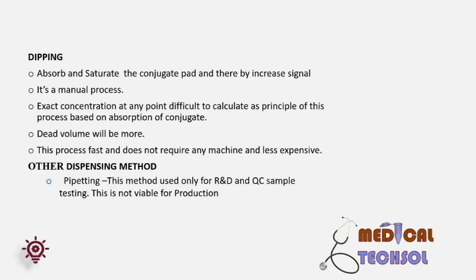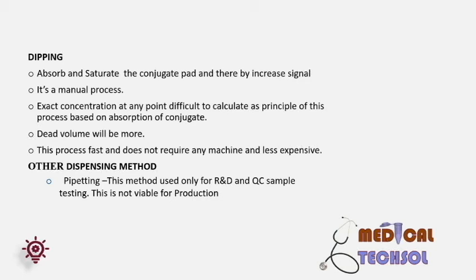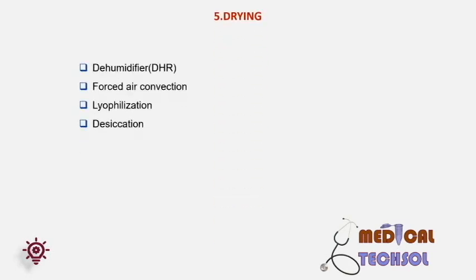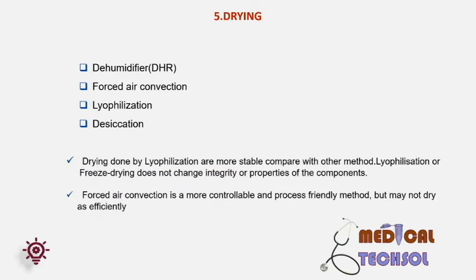Other dispensing methods include pipetting, which is only for R&D or QC sample testing and not viable for production. Drying — conjugate drying is a critical factor, done by: 1. Dehumidifier (DHR) method — sample is kept in a DHR room to dry. 2. Forced air convection — more controllable and process-friendly but may not dry efficiently. 3. Lyophilization or freeze drying — more stable compared to other methods and does not change the integrity or property of the component; however, samples are loosely bound to the pad after drying, requiring extra care. 4. Desiccation — time consuming and hence not suitable for production.